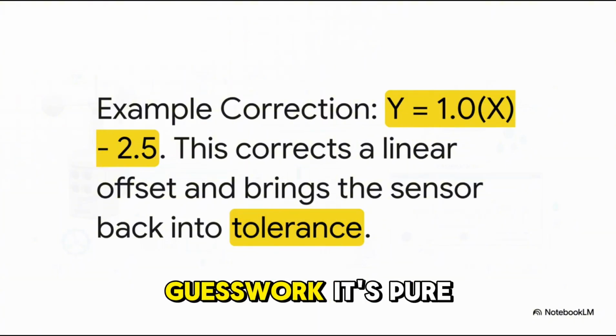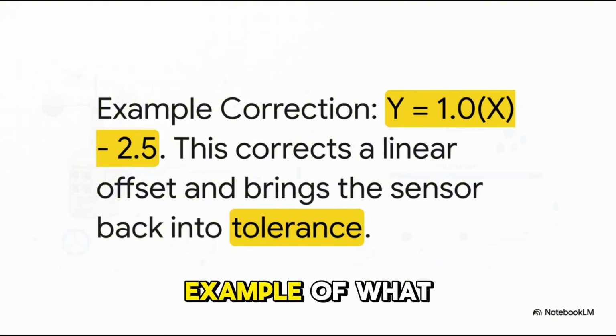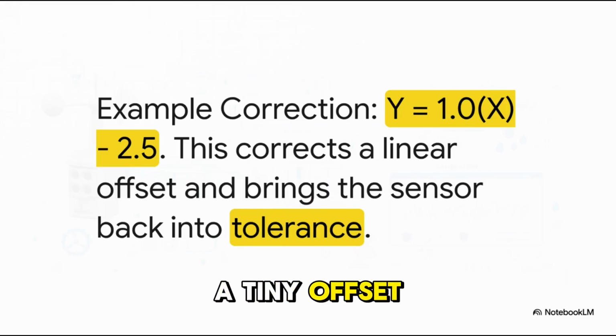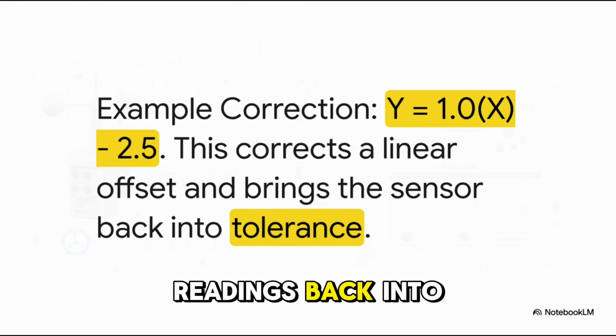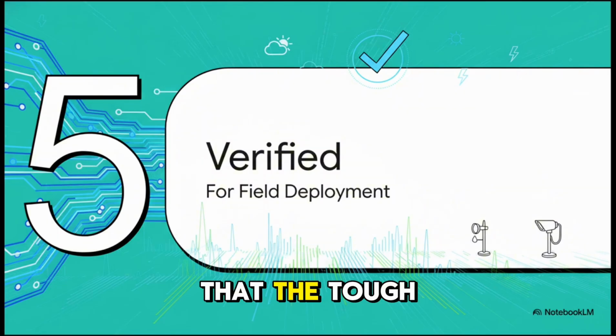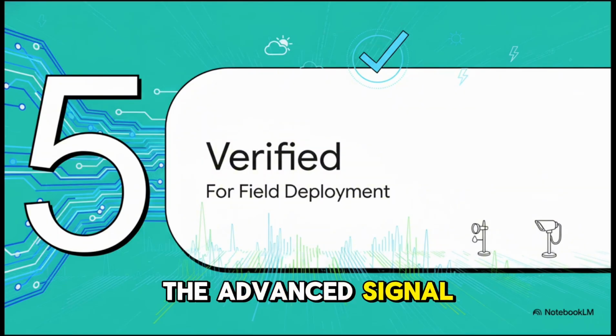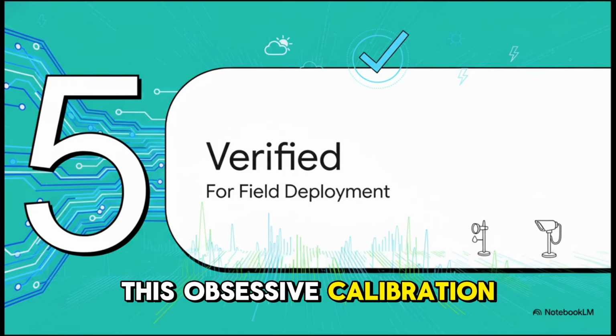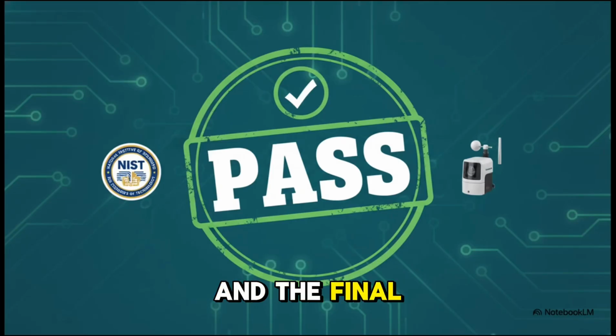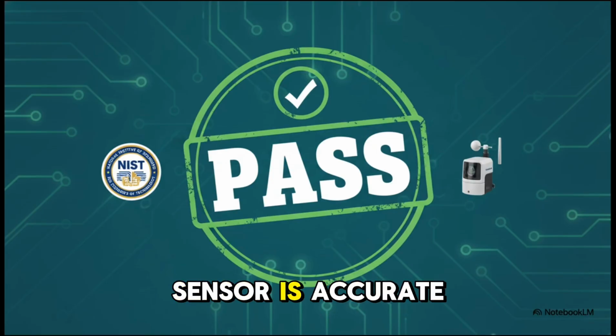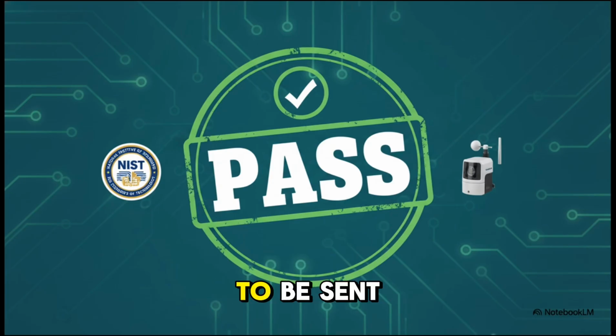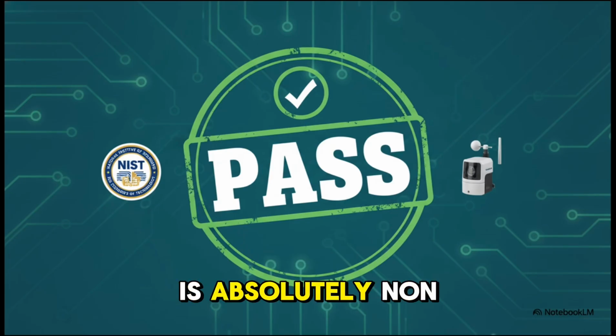And this isn't guesswork, it's pure math. The source even gives us an example of what this fix looks like. A tiny offset was found, so this exact formula, y equals 1.0 times x minus 2.5, was programmed right into the sensor's software. It's a surgical adjustment to bring its readings back into perfect alignment. And all of that, the tough, solid-state design, the advanced signal processing, this obsessive calibration, it all leads to the final result. And the final verdict is just one simple word, but it means everything: pass. That confirms the sensor is accurate against the ultimate standard, and it's ready to be sent out into the field where its accuracy is absolutely non-negotiable.